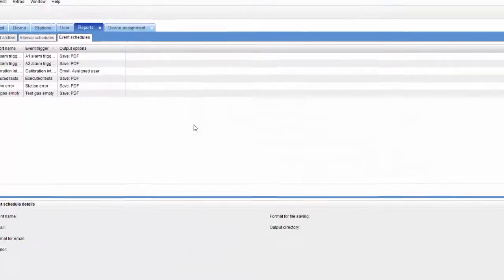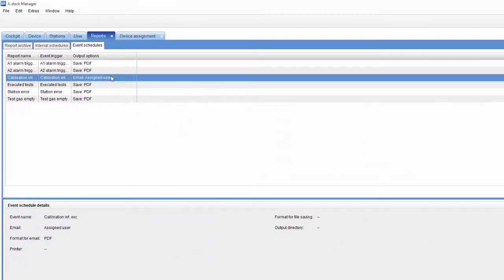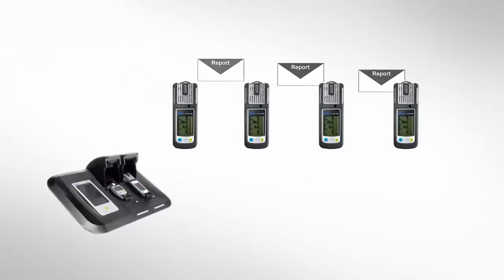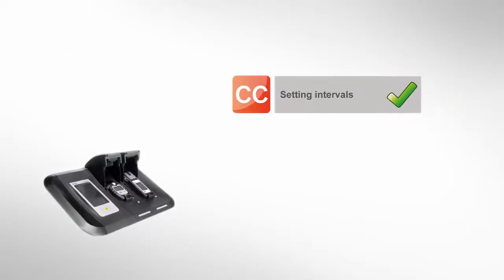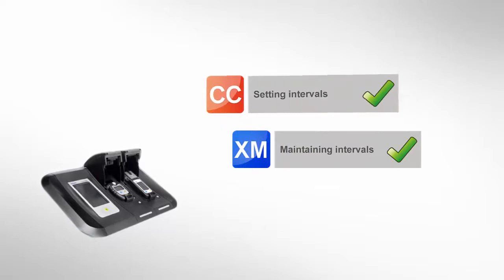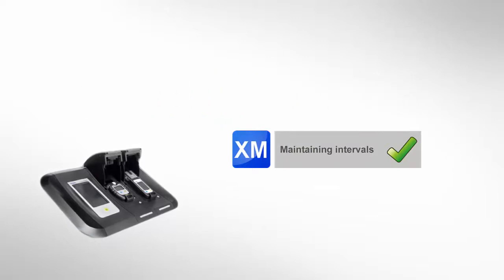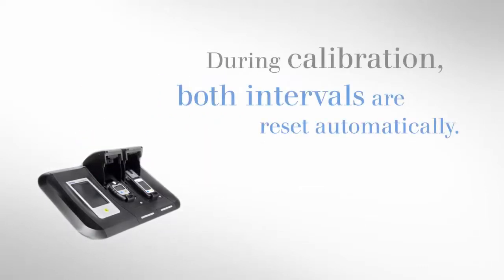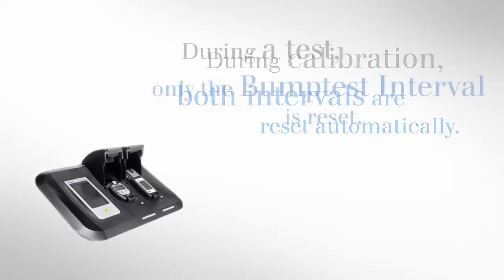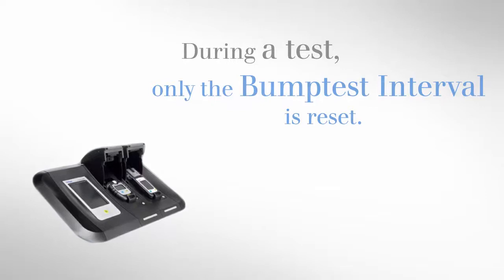This report will be created for each individual device and only when the calibration becomes overdue. This means that we will not receive a report now, but only when the next gas detector becomes overdue. In this tutorial, we have seen how to define and maintain intervals. By the way, after a successful calibration, both intervals are reset. After a successful test, only the bump test interval is reset.